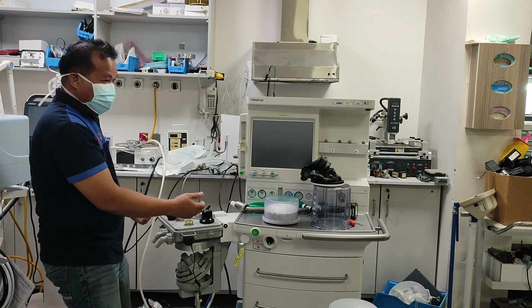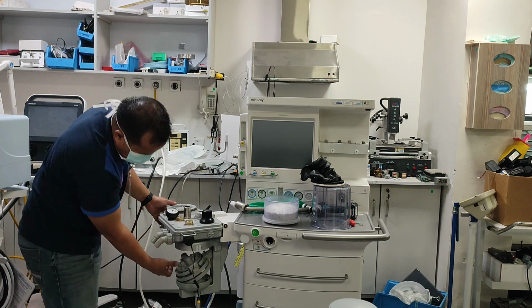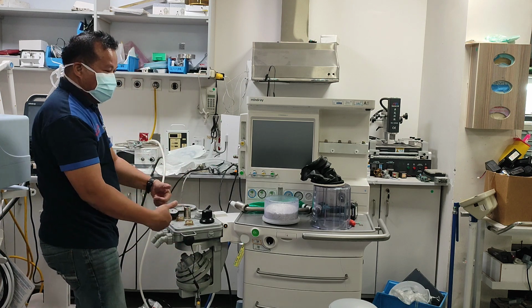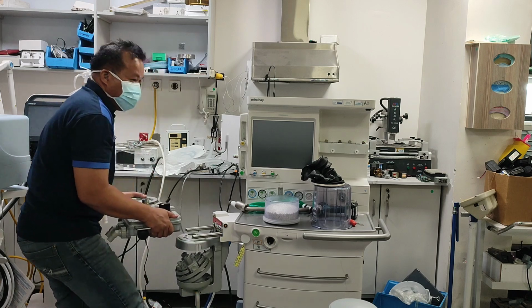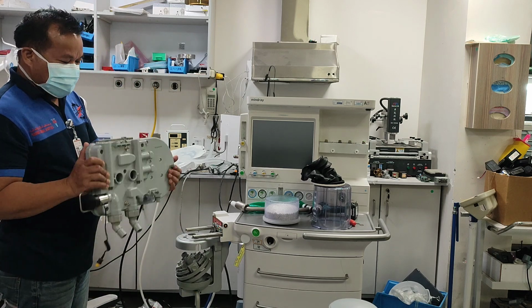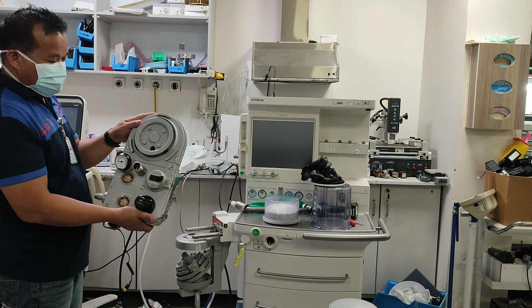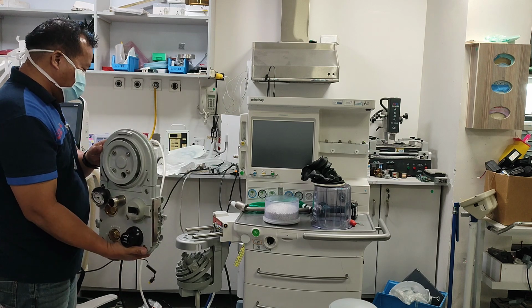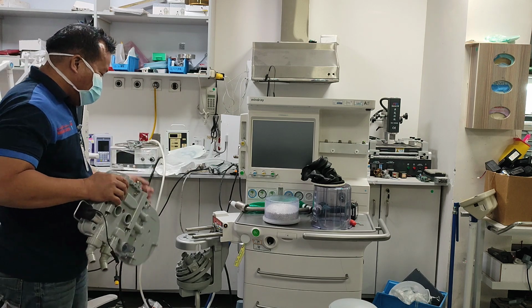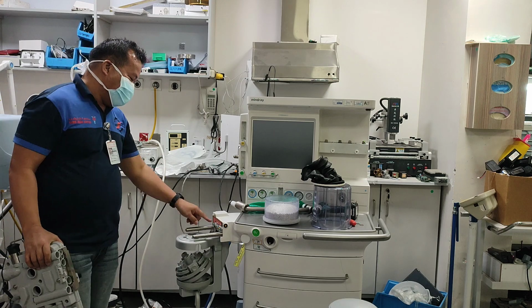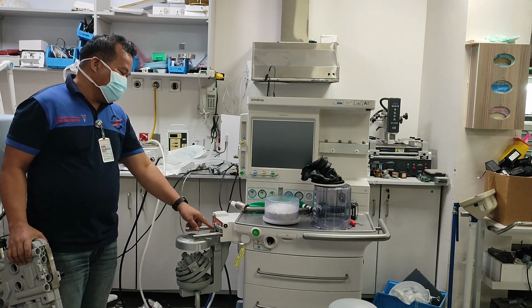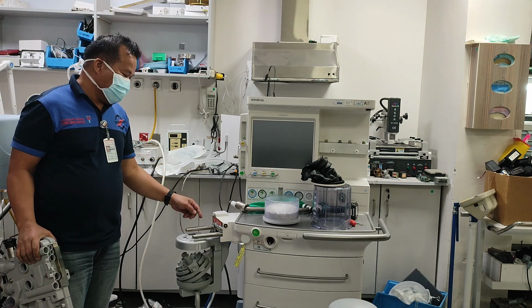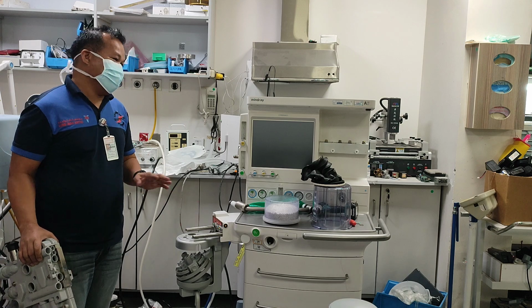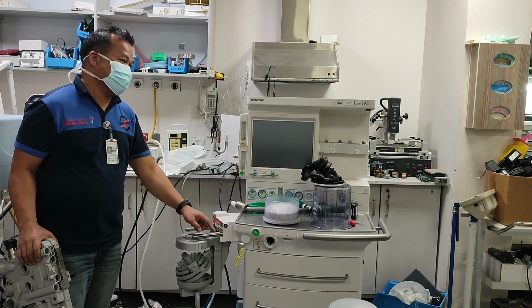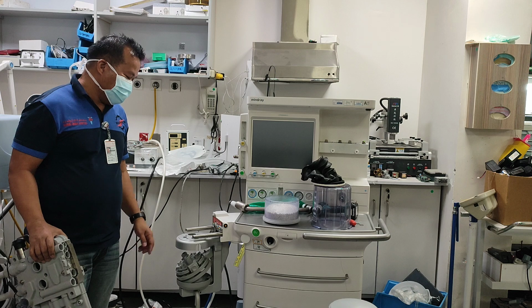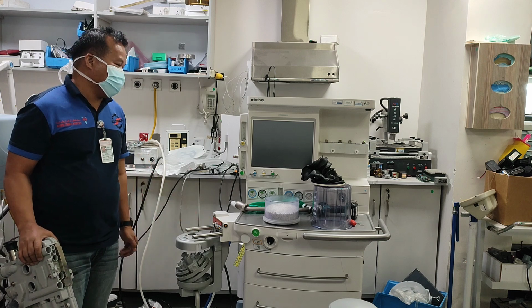So it will not pull once it is connected. So you should remove this cover. Just press on the two buttons. Then you can easily remove. So this is the patient module block. So during PM you should replace all this gasket here. Every 6 months, once you do a PM, preventive maintenance of the machine, you should change this old gasket. This is the consumable only. Every 6 months you need to change.